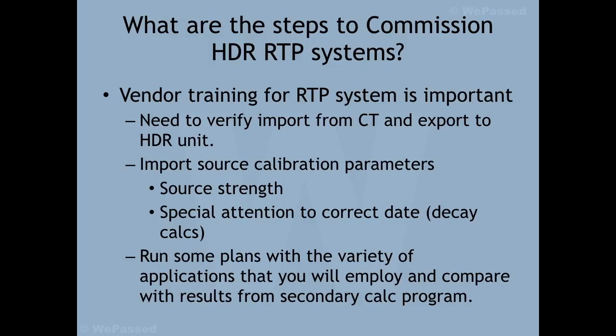When you're going to commission your new HDR system with a treatment planning system, you need to know your HDR planning system well. For example, you need to get training from the manufacturer, learn how to do planning and how to import and export images, and make sure you've done the tests for commissioning the planning system, including CT communication with your treatment planning system, and your treatment planning system with your HDR console.